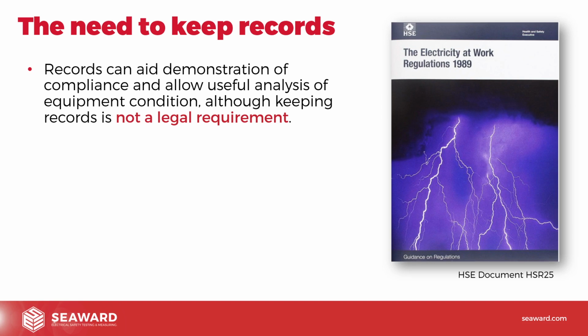Now it also allows analysis of the equipment condition. So again, you can look for patterns and trends. If you've got a particular make of drill that keeps breaking, that's a trend, that's a pattern, that's something you need to be doing something about. You can be preemptive. You can say, look, we've had 3 of these drills go wrong, we've got 5 of them in total, let's have a look at the other 2. Those sorts of patterns and trends you can identify, and that's really important. But always remember, record keeping isn't actually required by the Electricity at Work Regulations, by the law, but it is very useful to be able to do these things.